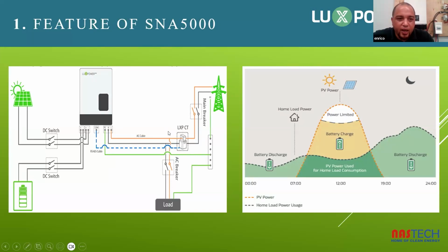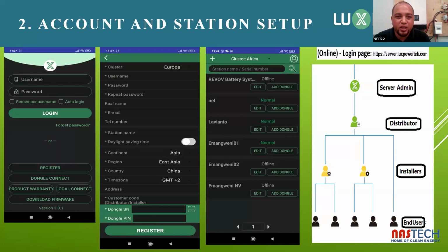Now, the reason why it's an LXP CT clamp is because this clamp is shipped standard with the LXP models of our inverter. The LXP range has a higher IP rating. So it's a complete off-grid inverter, and you are capable of installing that particular inverter outdoors. That's the reason for the difference in the costing of the two inverters. This one is for indoor installation, and our LXP will be for outdoor installation. Yes, so these are the features. We will continue to go through all the features in the presentation.